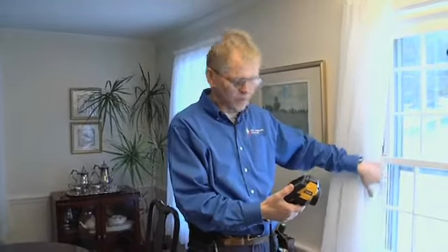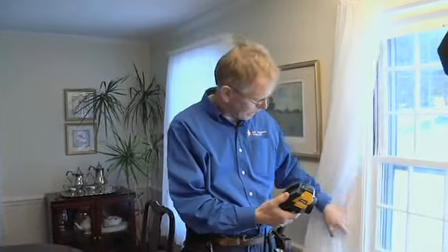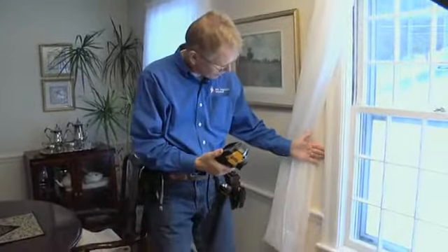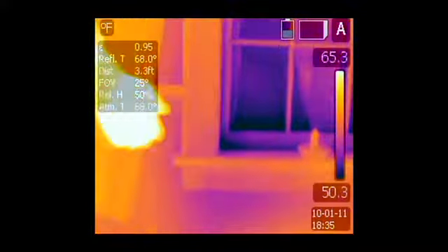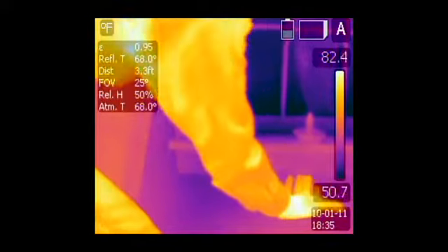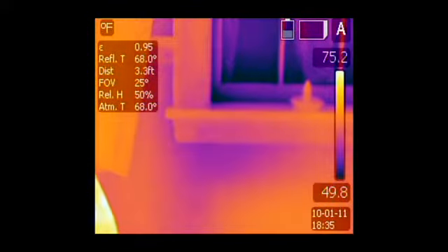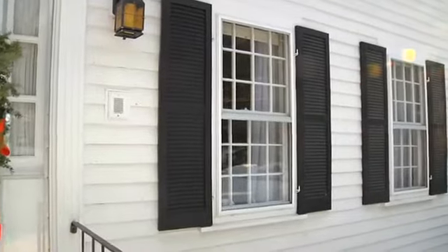Yeah, actually on the window, if you want to keep the old window, I recommend weather stripping and gaskets around the window, and maybe caulking along the edges here, and especially down on the bottom and on the top of the window. That's often where they forget to caulk. And again, it's simple fixes. It doesn't cost a fortune to do these.